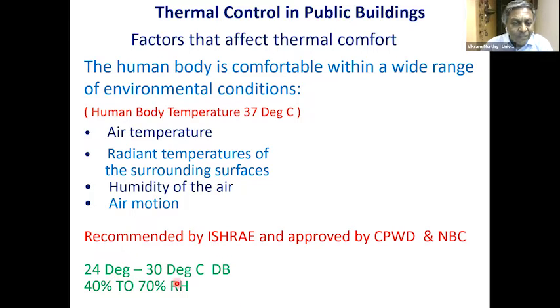ASHRAE in 2020 came out with a standard to battle COVID, where we said you can maintain temperature between 24 and 30, depending on conditions. If you're in a dry place, maintain a higher temperature; if you're in a humid place, maintain a lower temperature. This is a way to adapt and reduce energy use.